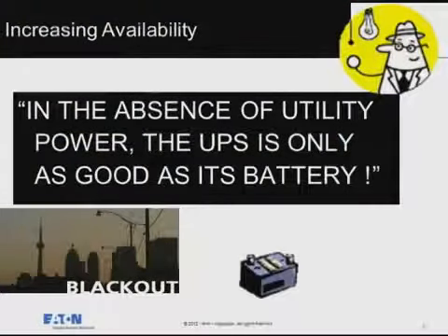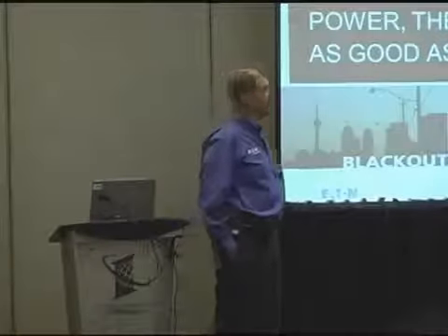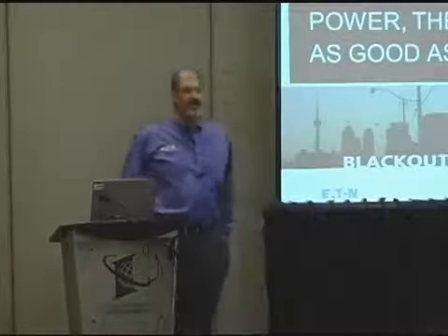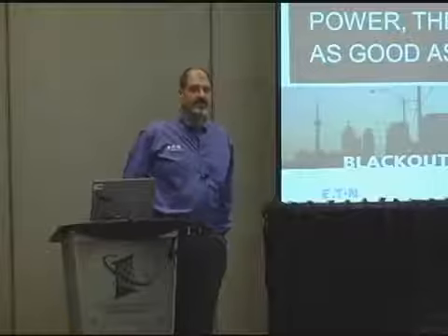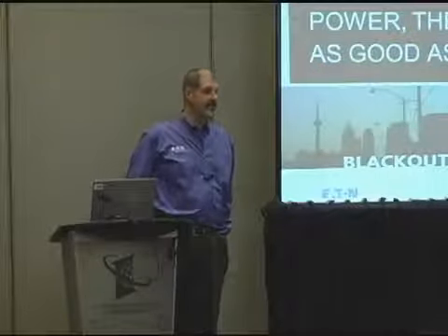The next piece I want to discuss is, quite frankly, the Achilles heel of UPSs. Far too often I get the call saying the UPS failed. Well, with all due respect, it wasn't the UPS, it was the battery that failed. The battery is a consumable device. It is the lifeline. Typically, that's by far the number one scenario under which the UPS fails to perform its functionality, because the battery has been consumed.